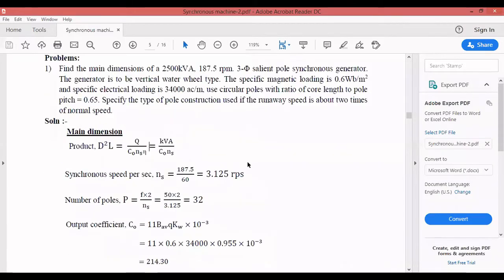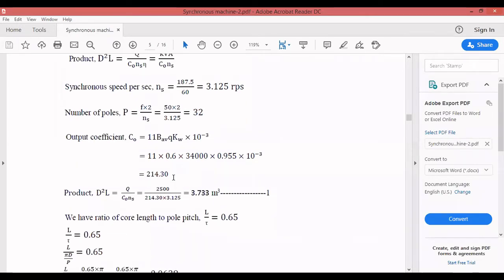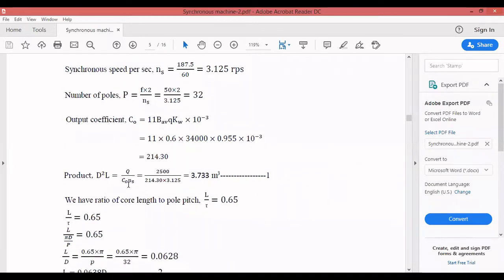The output coefficient C₀ = 11 × Bav × ac × kw × 10⁻³. The winding factor kw is not given, so we assume 0.955 as is standard. Bav = 0.6, ac = 34,000, kw = 0.955, giving C₀ ≈ 214.30. The product D²L = Q / (C₀ × ns) = 2500 / (214.30 × 3.125) ≈ 3.733 m³.